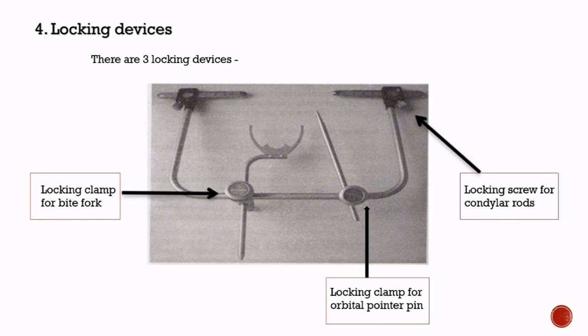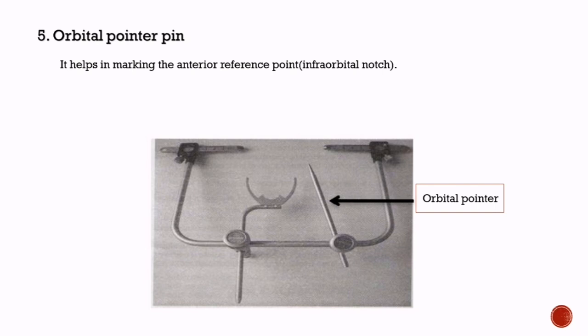Fourth is locking devices. There are three locking devices: a locking clamp for the bite fork, which attaches the bite fork to the U-shaped frame; a locking clamp for the orbital pointer pin, which locks the orbital pin onto the U-shaped rod; and a locking screw for the condylar rods. Fifth is the orbital pointer pin, which helps in marking the anterior reference point, that is the infraorbital notch, and it is present only in the arbitrary face bow.